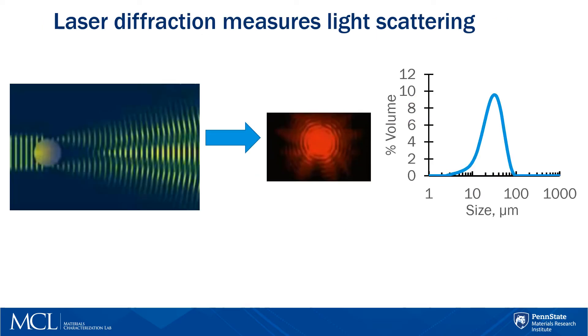The particle is hit with a monochromatic light and light is diffracted from its edge. This begins to create waves that overlap and create an interference or diffraction pattern. You can see radiating lines — black lines mean destructive interference of waves, and bright lines mean constructive interference. From the diffraction pattern we can derive size information.